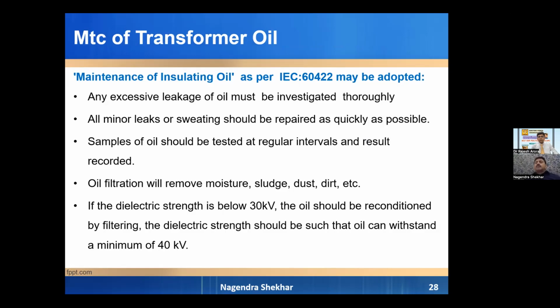We have to maintain transformer oil also, because it is something which keeps our transformer functioning properly. If there is any excessive leakage of transformer oil, we have to check it thoroughly and stop it. Minor leakages we have to address immediately. For major leakage, if required, we have to send our transformer to the transformer workshop. Minor leakages can be repaired at site. We have to check the dielectric strength of our transformer oil; the BDV should not be less than 40 kV.